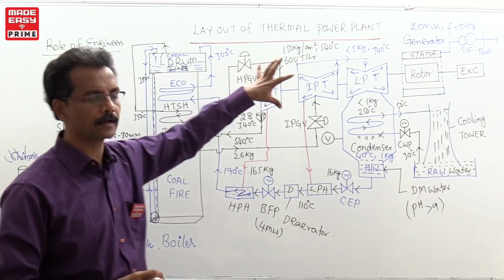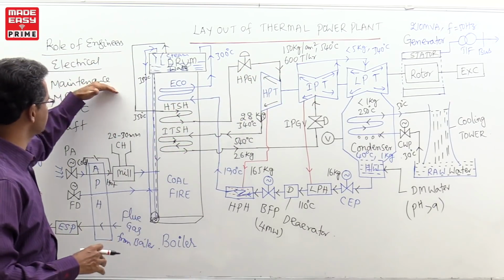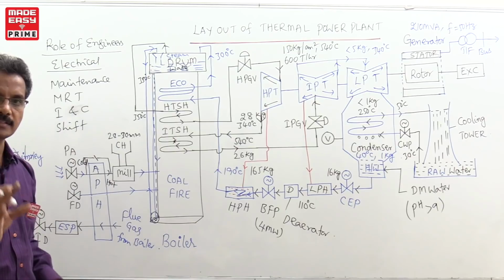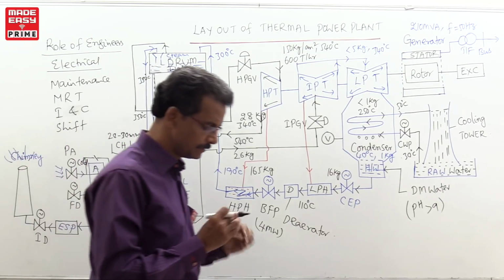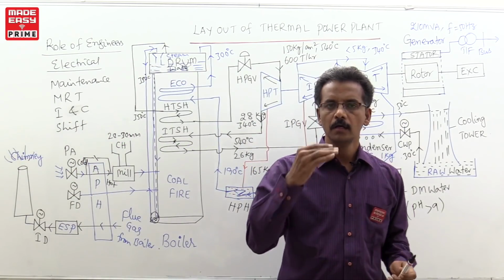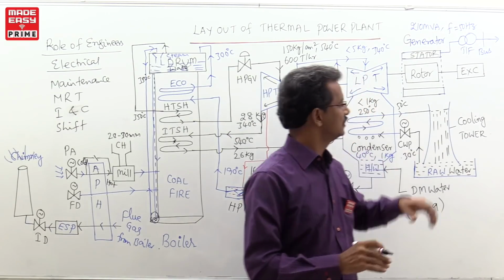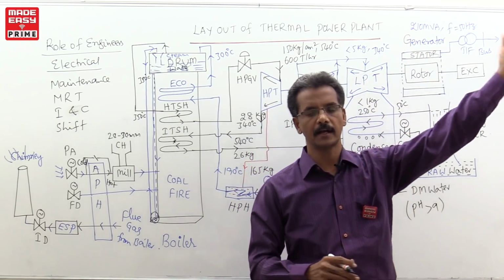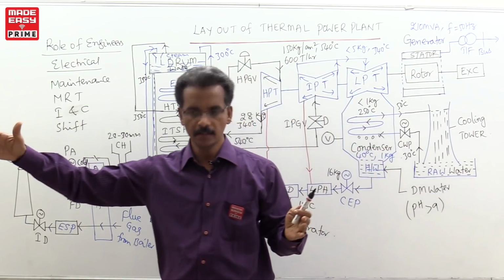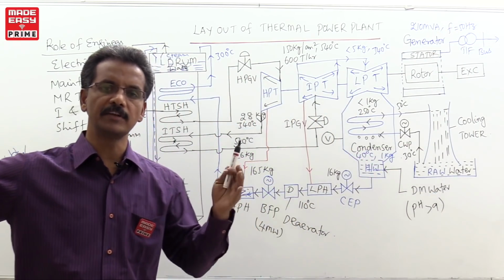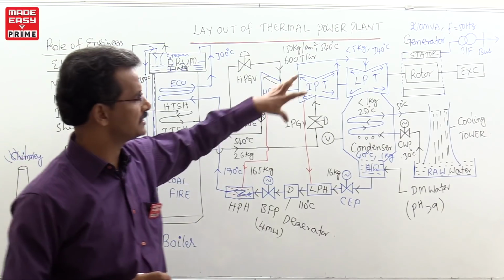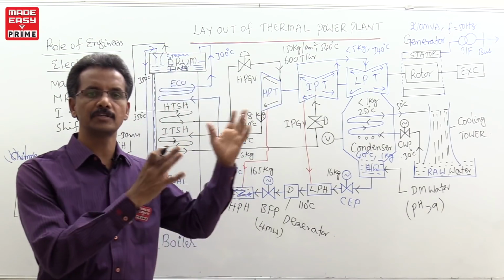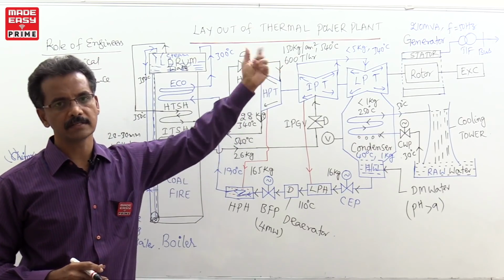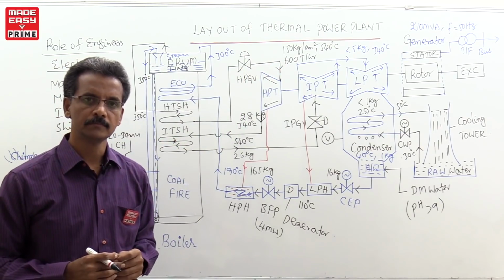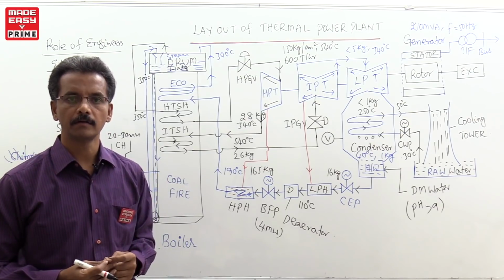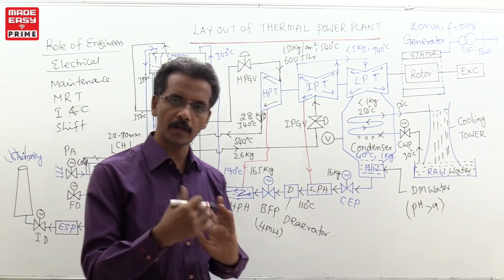Those things will be taken care of by engineers in maintenance as well as MRT. MRT means meters, relays and testing. They will periodically do the testing of relays. Suppose this generating station is connected to the transmission line. For the transmission line, what we have studied in regular class is the distance relay. Or think of generator protection. In generator protection, you use the percentage differential relay. For a transformer, a percentage differential relay in combination with others. Whether these relays are functioning or not, they have to do periodical testing, including overcurrent relays.